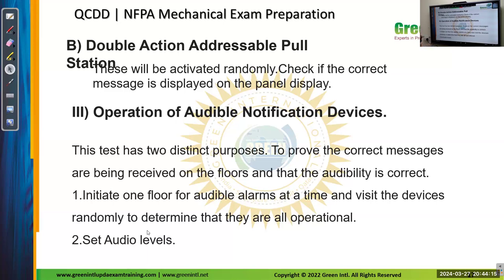So, operation of audible notification devices. This test has 2 distinct purposes to prove the correct message is being given. So these are all some information that is a sort of checklist to do the inspection of these devices, and we have to make sure that the intended specification is met or not.